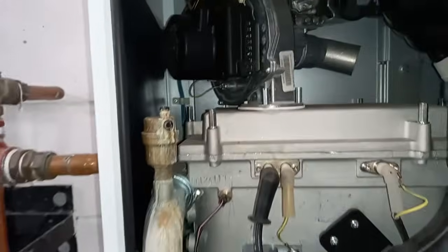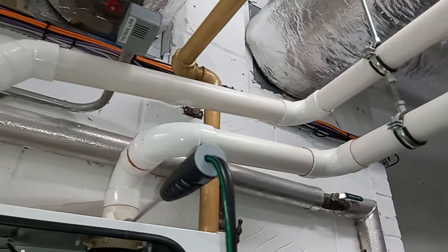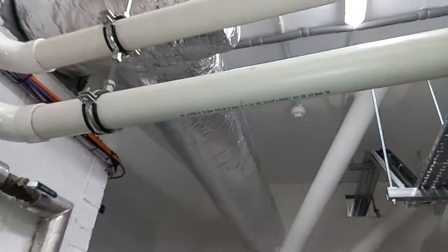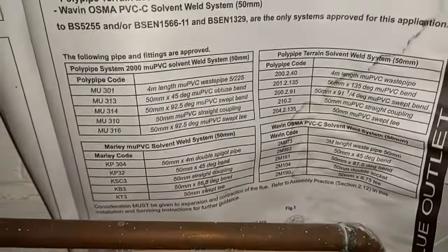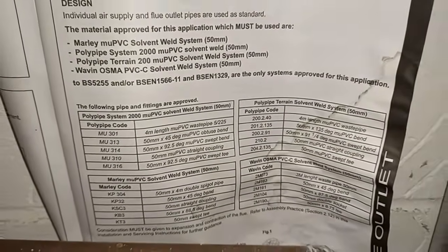So, back to the boiler. This is a Keston boiler. Watch out for these flues because often they're made of the wrong material, so you need to look up here and check in the manual what type of material they want the flue to be made of. Other things to check on the flue include making sure they're properly clipped.